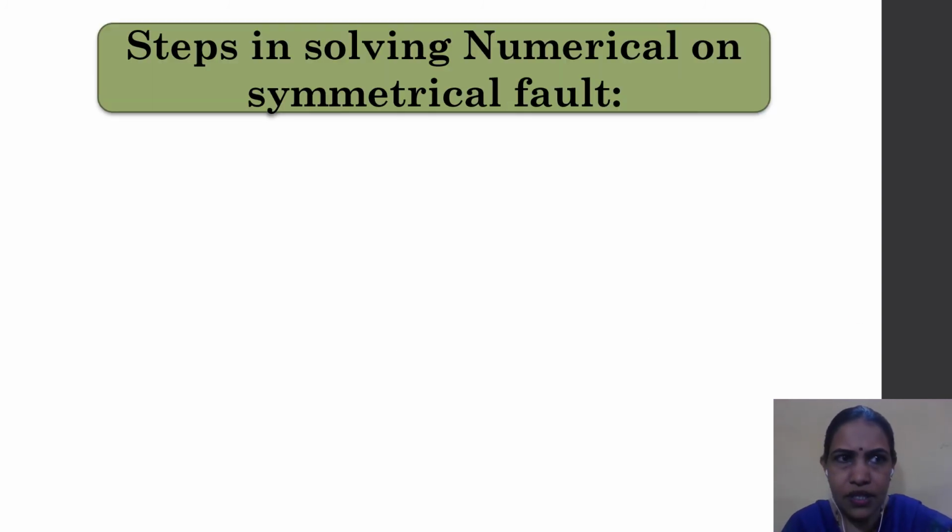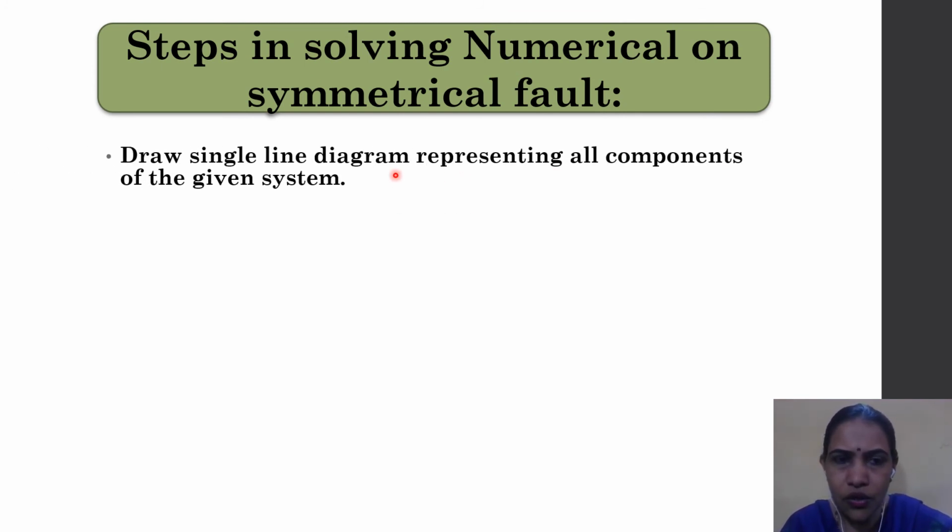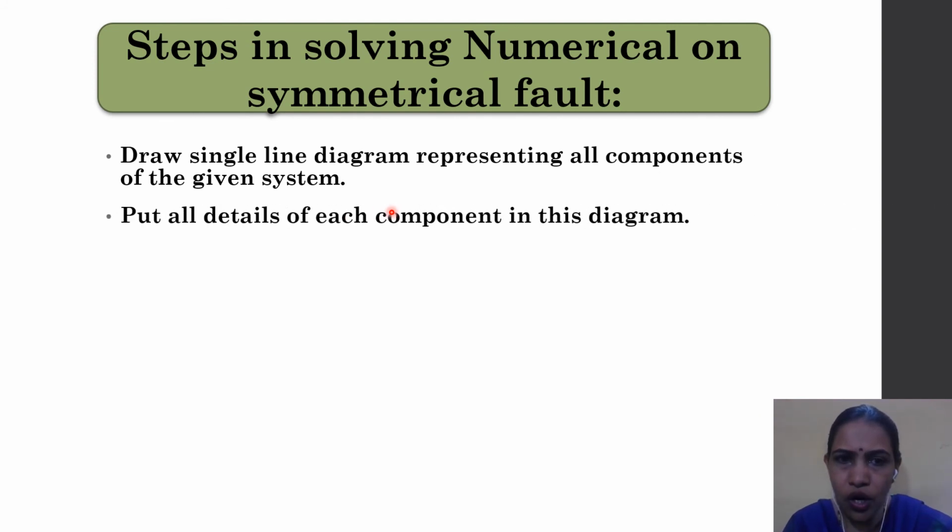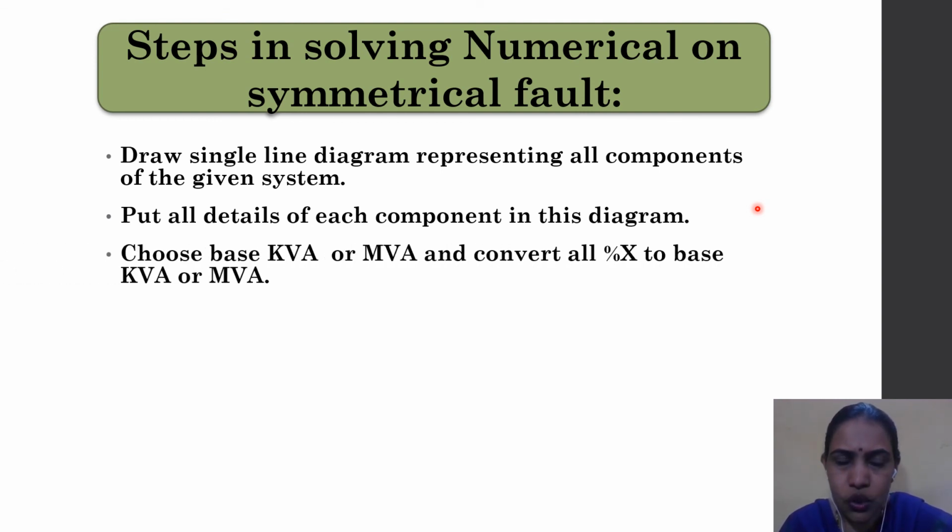So let's summarize all the steps which we have already covered in solving numericals on symmetrical fault. First, you have to draw a single line diagram representing all components of the given system. Then put all details of each component in this diagram, so you note down all things related to each component in the power system. Choose base kVA or base MVA and convert all percentage reactances to the base kVA or base MVA.